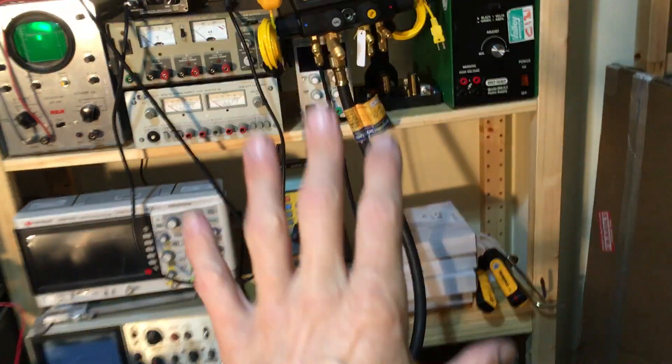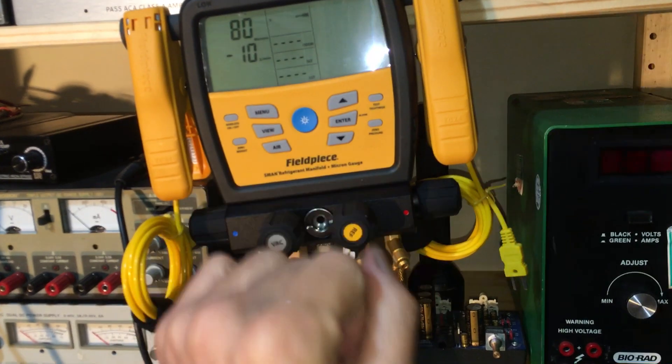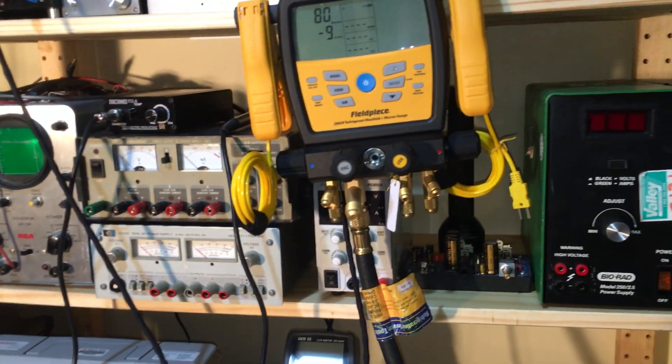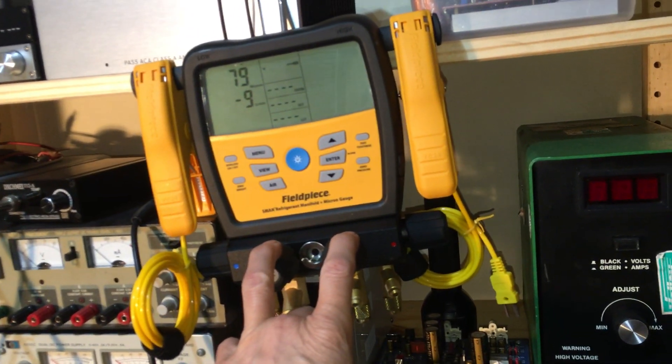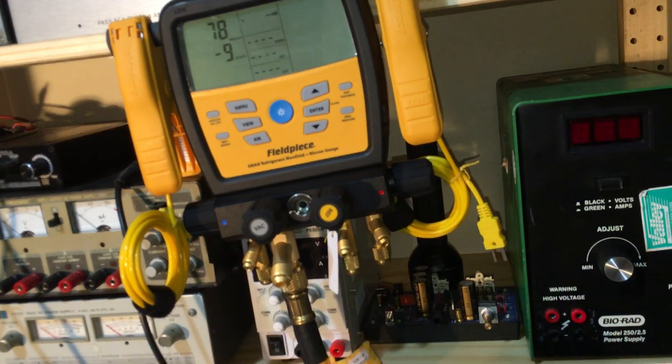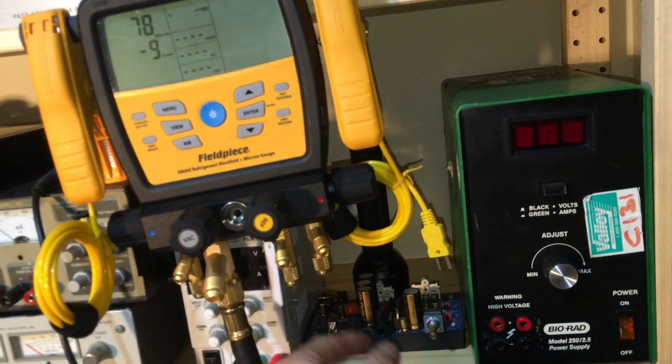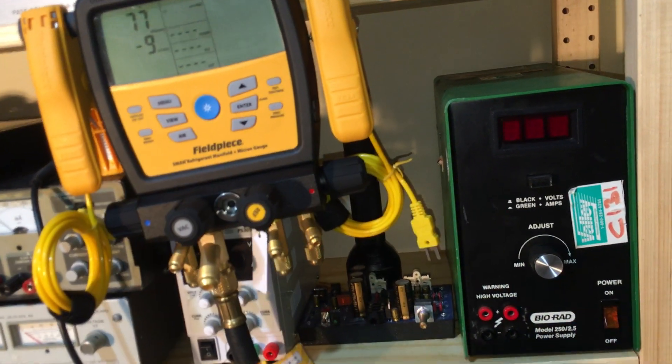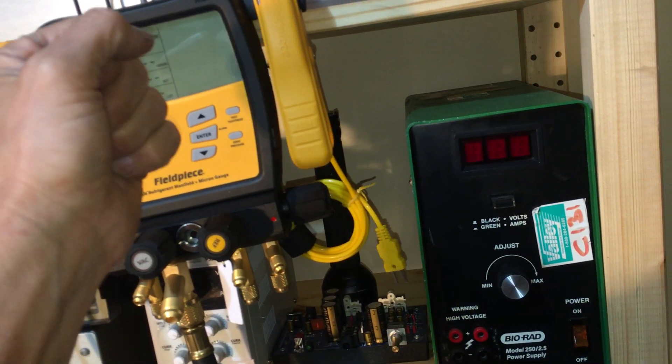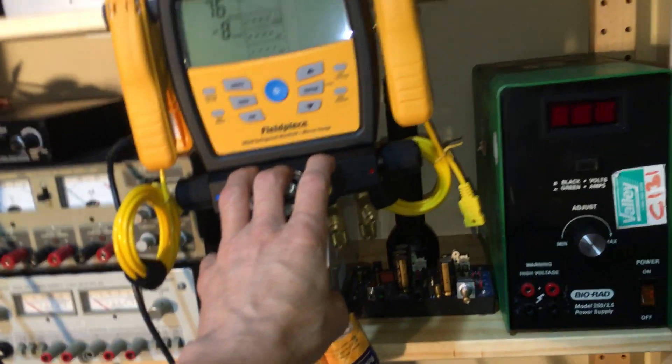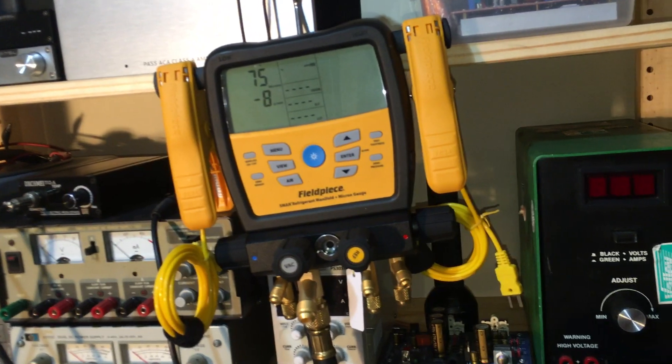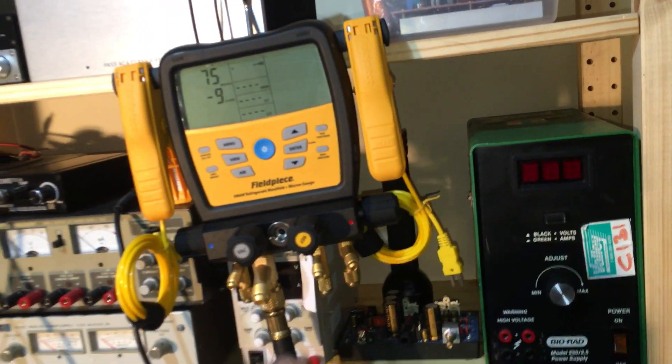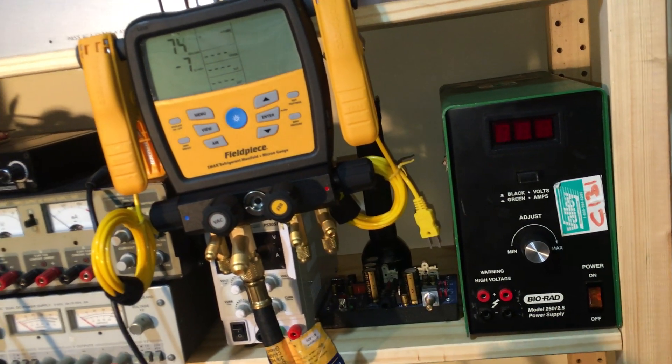So this is the first step of me commissioning in a set of gauges before they ever hit the field. Then there'll be a nitrogen pressure decay test and I'll hold it overnight. Actually, on my big units I use copper lines. I don't use gauges and there is no rubber in my system when I do a pressure decay test. It's all using soft copper as hoses onto a pressure. Actually I like my Testo 557 as my nitrogen pressure decay test tester when I do 24 hour nitrogen pressure decay test. That is my go-to thing with soft copper lines with no rubber gaskets.